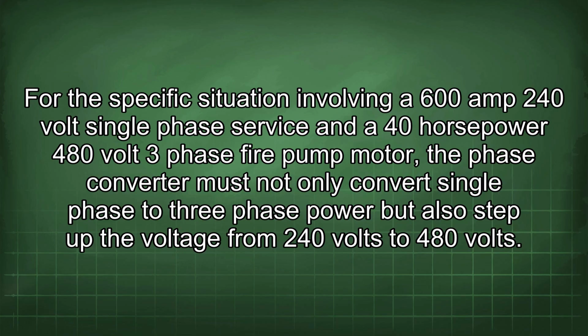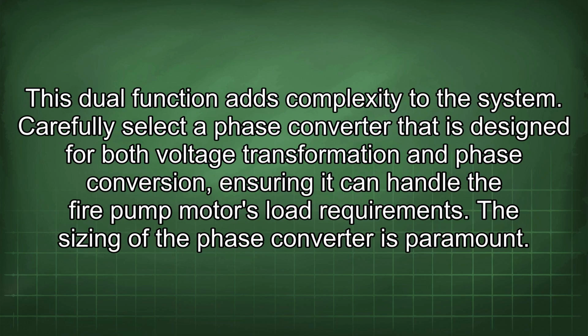For the specific situation involving a 600 amp 240 volt single-phase service and a 40 horsepower 480 volt three-phase fire pump motor, the phase converter must not only convert single-phase to three-phase power, but also step up the voltage from 240 volts to 480 volts. This dual function adds complexity to the system. Carefully select a phase converter that is designed for both voltage transformation and phase conversion, ensuring it can handle the fire pump motor's load requirement.